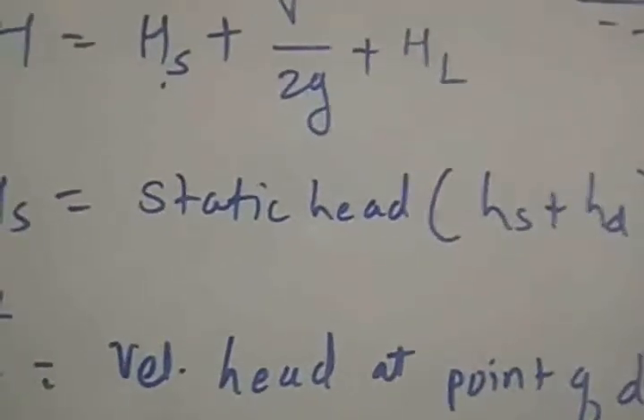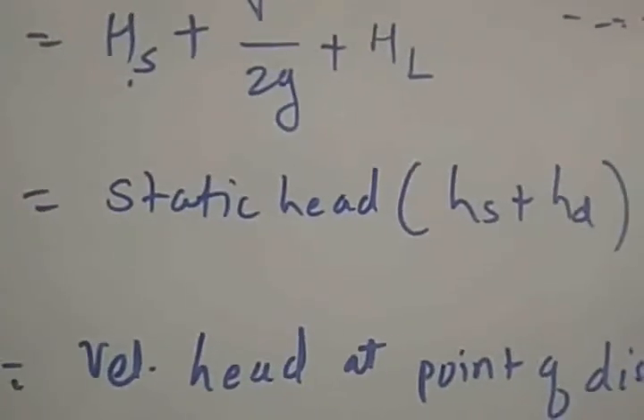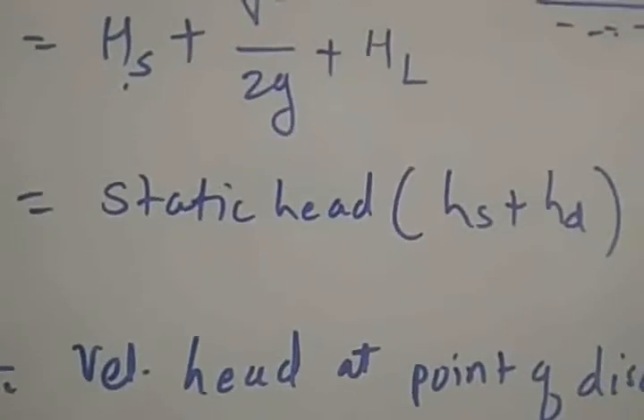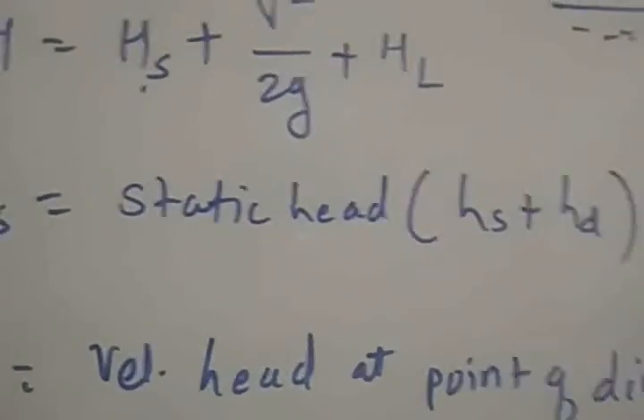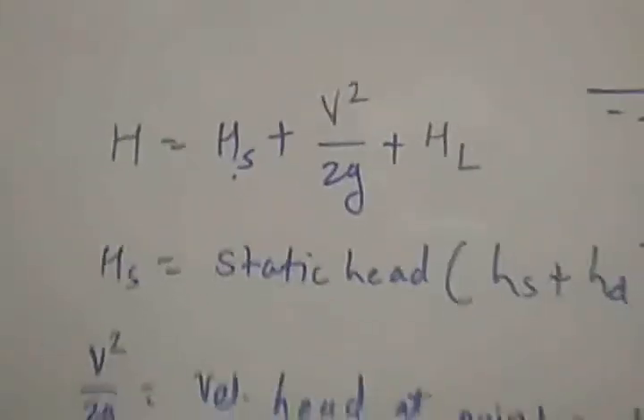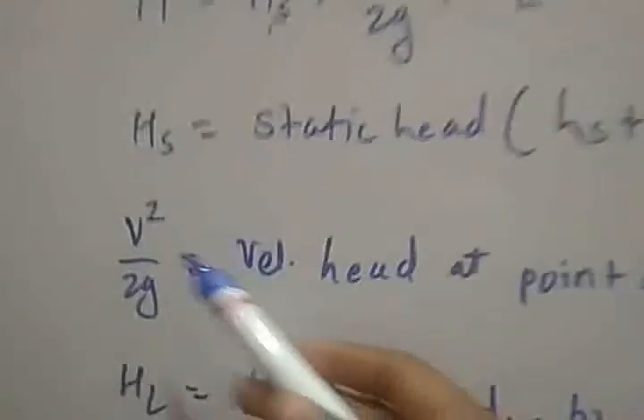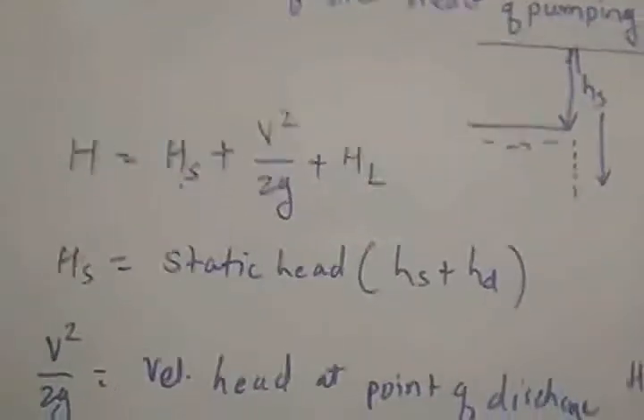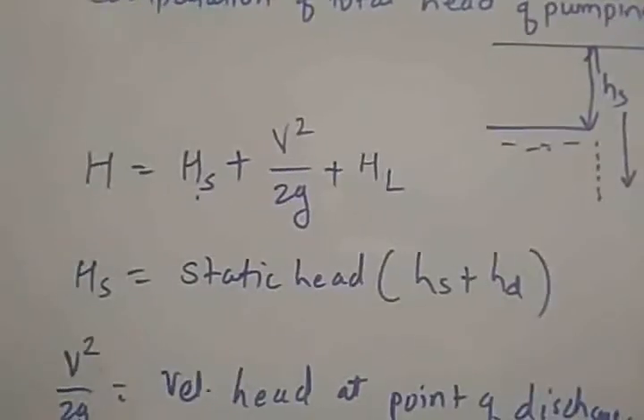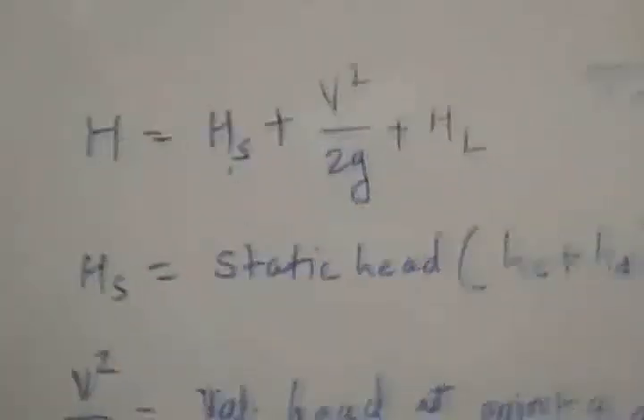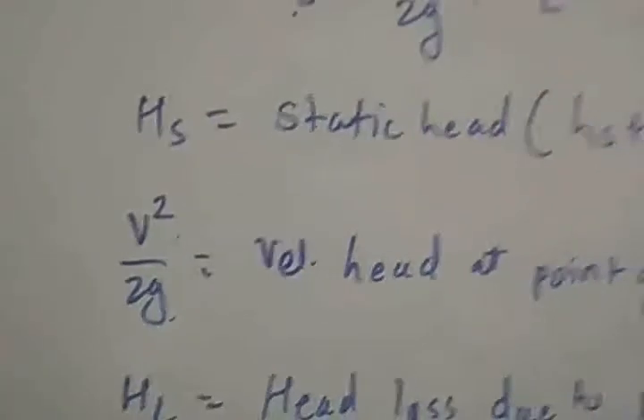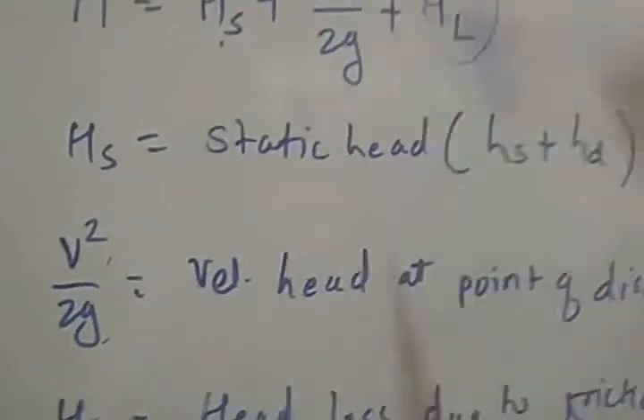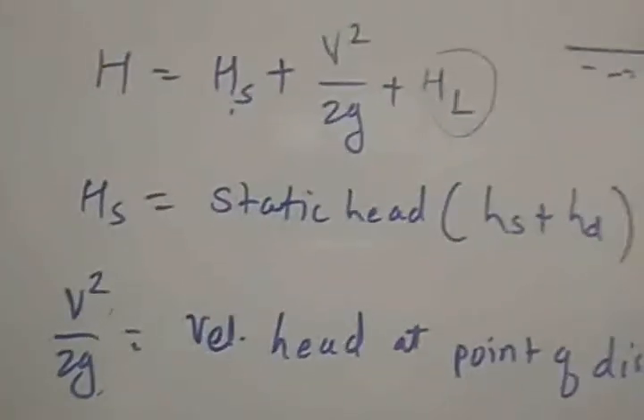Also, if the size of the pipe is changed, the velocity of flow will change, which will in turn change the velocity head. So when pipe size is changed, velocity will change and because of that velocity head will be changed. Static head will change because of the fall in the level of liquid. Changing pipe velocity will ultimately change the head loss due to friction.